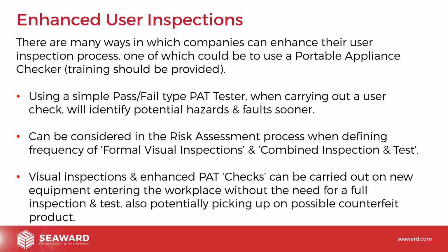Using a simple pass-fail type PAT tester like our Prime Test 50, when carrying out a user check, will identify potential hazards and faults sooner. So we're doing a user check, but giving that user the ability to check things like the insulation resistance and the earth continuity as well. So the things that historically might only have been picked up every 2 years when the person comes around to do a formal PAT test could now be picked up as part of an enhanced user check. So it's something that we think is quite an important change, and it's something that duty holders could factor into their processes.